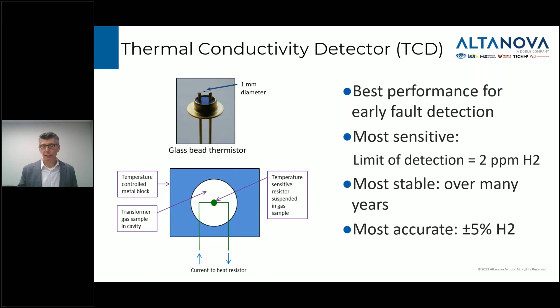And it turns out that if the gas around that thermistor is more thermally conductive, that is, if it contains more hydrogen, that thermistor will reach a lower temperature because it's conducting heat effectively through that hydrogen in the gas. So hydrogen is anomalously a conductive gas. It's 3 times more conductive than the other gases in this application. So it gives us leverage on detecting the presence of the hydrogen in the gas. We layer on top of this a number of other tricks in order to carefully isolate exactly the hydrogen and the carbon monoxide signatures.